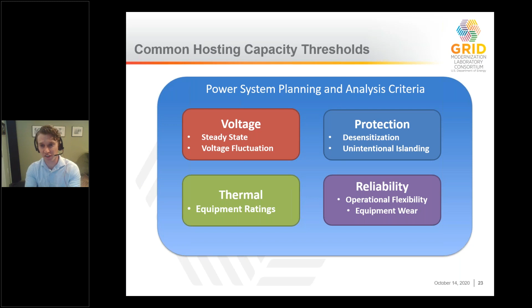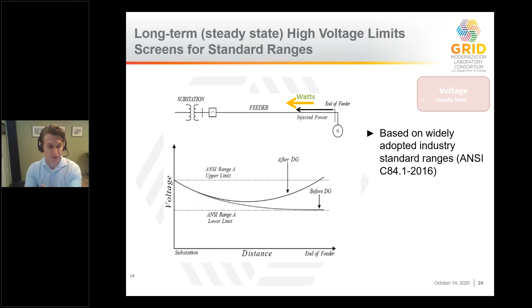This chart may look familiar if you sat in on my presentation from yesterday, but reverse power flow from DER can create high voltage, and there are set limits that equipment can tolerate. And so an important evaluation during hosting capacity is what the steady state voltage is going to be after DER. Next slide, please.